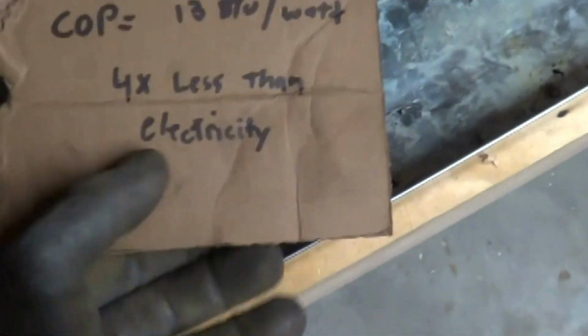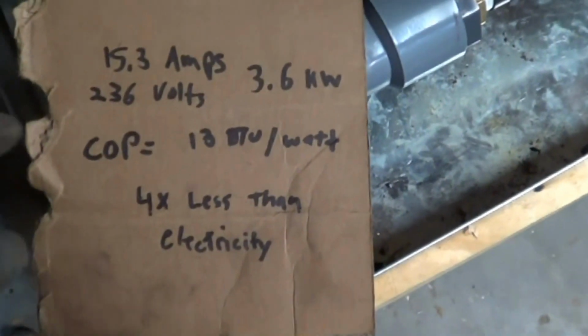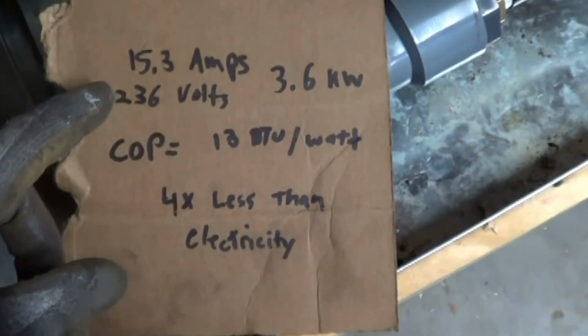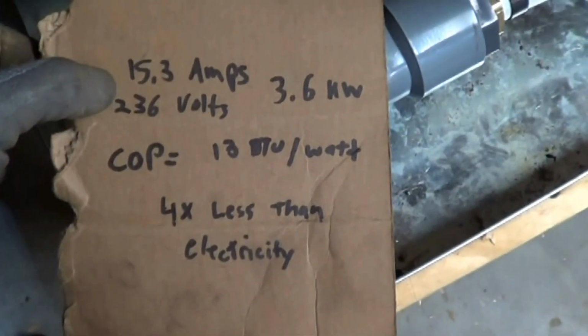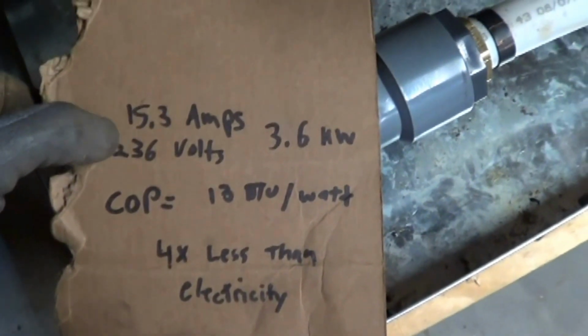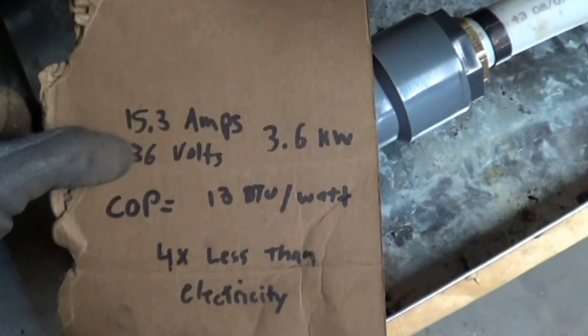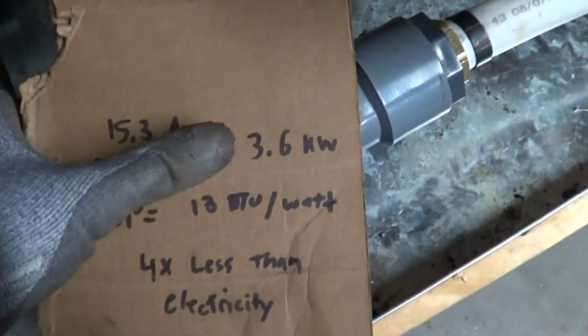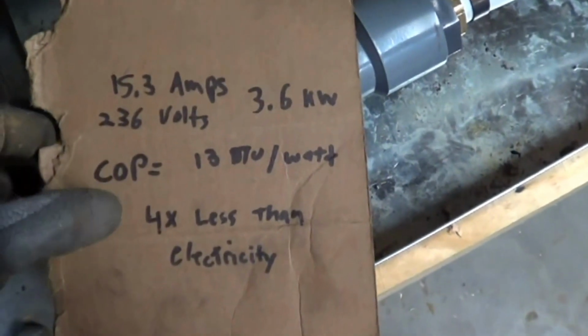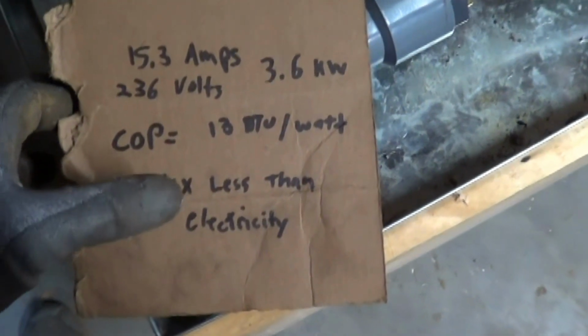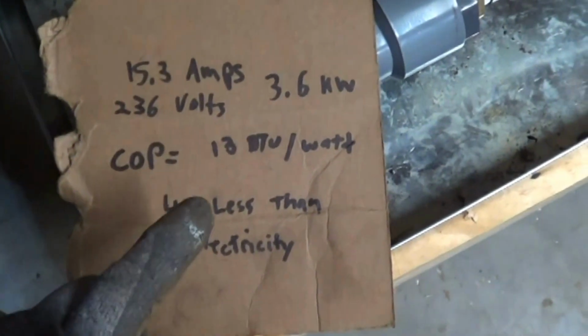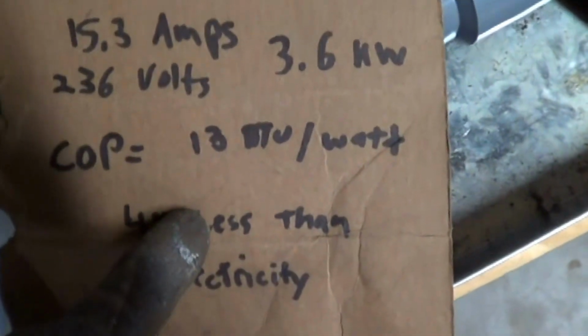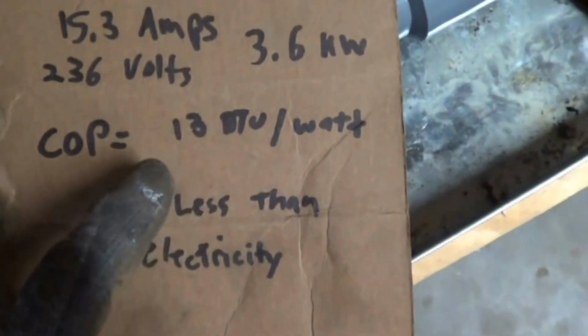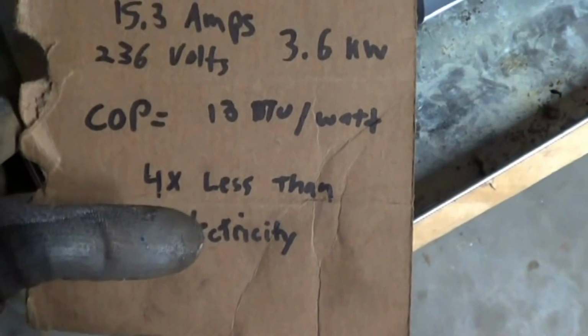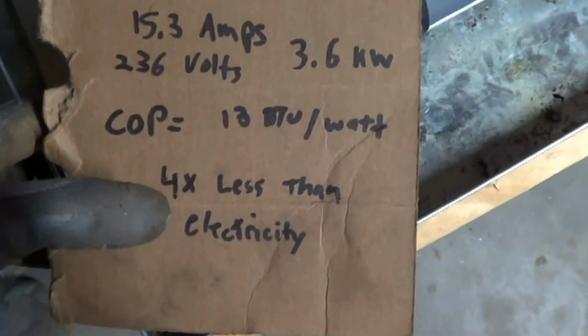And then a real quick looking at the power consumption. Now this doesn't have power factor, so it's going to be a little bit off. I don't have a true watt meter. Just use my amps times my volts. 3.6 kilowatts, and that's also including the pump. And then we have our output. We're running basically 13 BTUs per watt. That's 4 times more efficient than electricity.